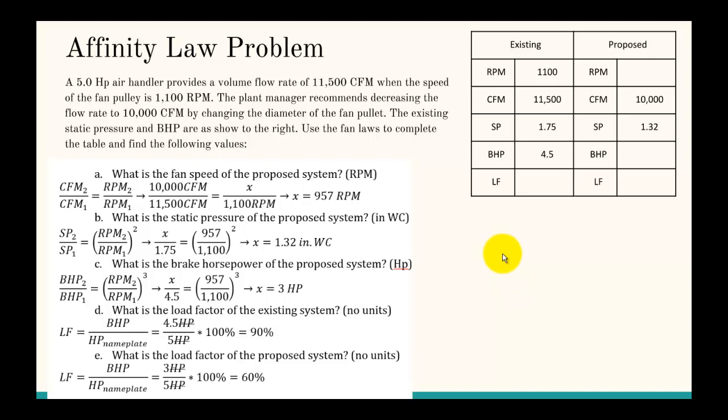The first one is what is the fan speed of the proposed system? We use this affinity law and plug in the values and solve for X, and the new speed would be 957 RPM. What's the static pressure? Same thing except here we use this affinity law and solve for X. Same thing with the brake horsepower.